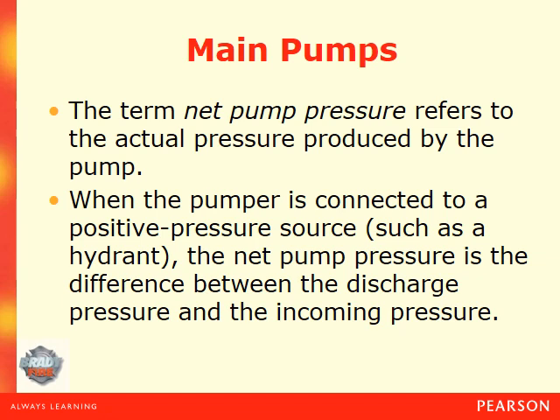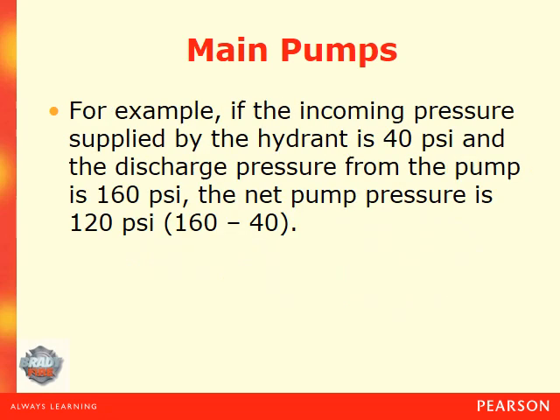The term net pump pressure refers to the actual pressure produced by the pump. When the pumper is connected to a positive pressure source, the net pump pressure is the difference between the discharge pressure and the incoming pressure. For example, if the incoming pressure supplied by the hydrant is 40 psi and the discharge pressure from the pump is 160 psi, the net pump pressure is 120 psi.